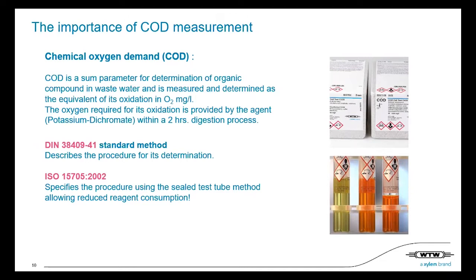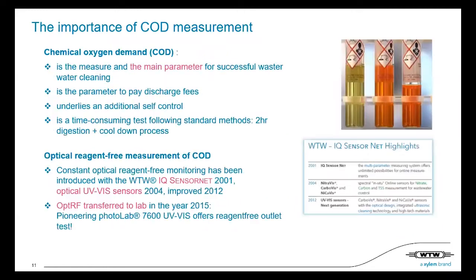It's a two-hour digestion process and cool down, and it takes quite some time. There are different standard methods describing the routine analysis, with an ISO regulation in 2002. Also, a smaller scale determination was given with cell tests, which you're probably using. This diminished the amount of agent and makes it more environmentally attractive. There are many ranges depending on whether you're measuring the inlet or outlet, so a wide range of testing kits. And it's important because worldwide, in many countries, it's the main parameter of successful wastewater cleaning.